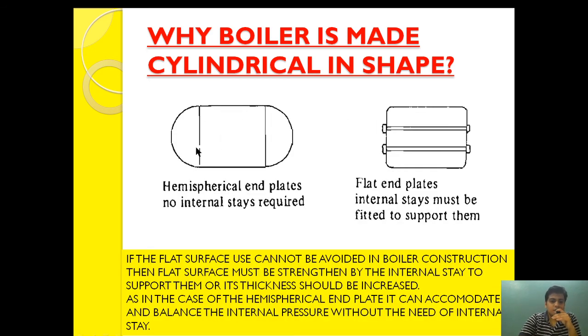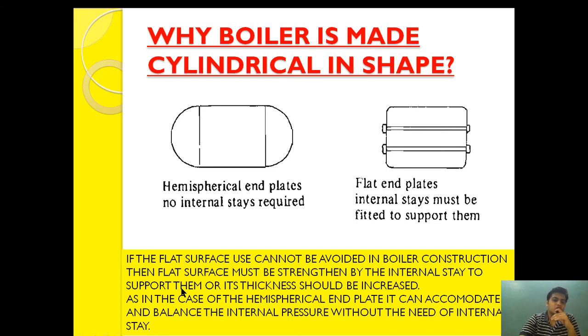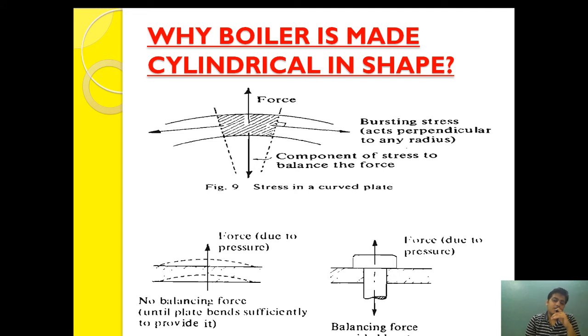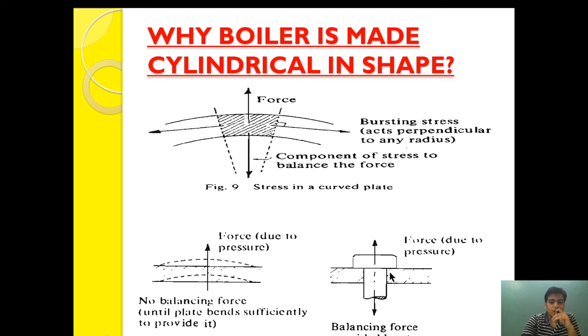The hemispherical end plate requires no internal stay, while the flat end plate requires an internal stay to support it. If a flat surface cannot be avoided in boiler construction, it must be strengthened by internal stays to support it, or its thickness would need to be increased. Our conclusion is that if we are not using a cylindrical surface, the flat surface must either have increased thickness or be supported with stays.